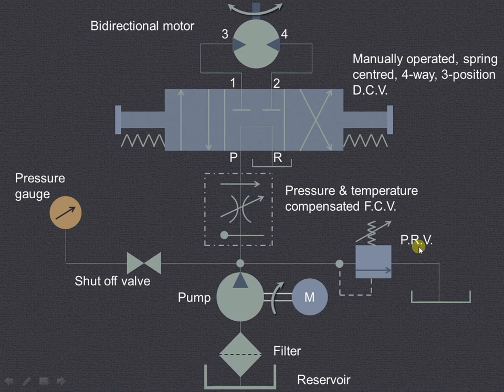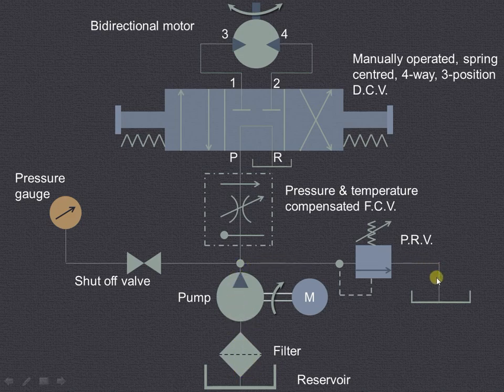If the pressure exceeds the design pressure, it will be sensed by this pressure relief valve, which is normally closed. If the pressure exceeds the design pressure, it will open and through this arrow — which will get shifted upward — the liquid will be delivered back to the reservoir. The pump will pump liquid from the reservoir, and it will keep going back to the reservoir through this particular path.